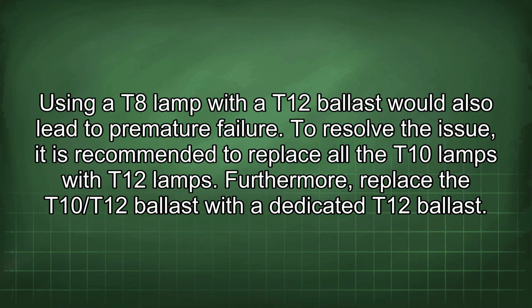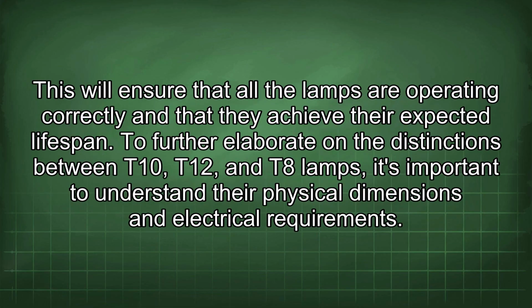To resolve the issue, it is recommended to replace all the T10 lamps with T12 lamps. Furthermore, replace the T10/T12 ballast with a dedicated T12 ballast. This will ensure that all the lamps are operating correctly and that they achieve their expected lifespan.